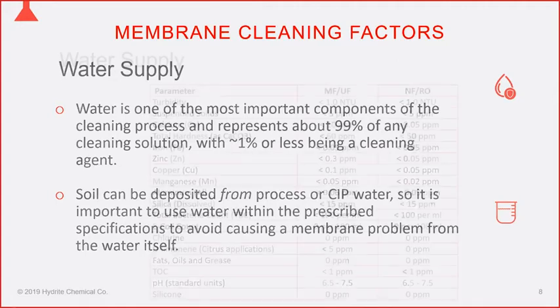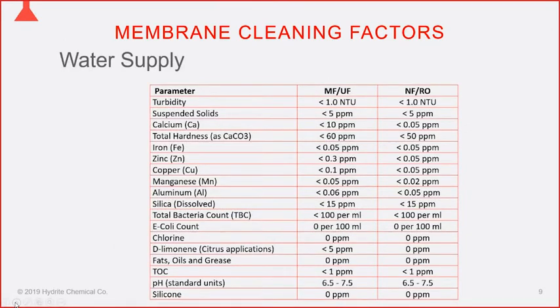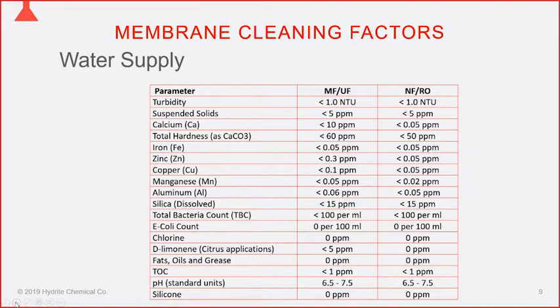Be aware that soil can come not just from what's being processed but also from the water. There is a reference chart listing water requirements for cleaning membranes, split between MFs/UFs — which are more tolerant — and NFs/ROs, listing contaminants of concern and their maximum contaminant levels. One key parameter to note is silicone, typically found in defoamers or anti-foaming agents, which none of the membrane types tolerate well.